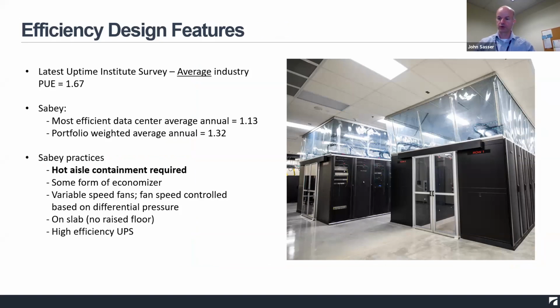So I've been with Sabey for 17 years, and we've been leasing data center space to customers for over 20 years. And efficiency has always been something that's very important to us. The latest Uptime Institute survey, and this is as of 2019, so it may be a little bit dated, but I don't think it's changed much, is that according to their survey, the average industry PUE was 1.67. At Sabey, our most efficient data center average annual PUE is 1.13, and our portfolio weighted average annual is 1.32. And people have talked about PUE, and I think a lot of people understand what it is, but for those who might not understand, it's essentially a measure of energy overhead. So a perfect PUE is 1. Anything above 1 indicates energy being used by something other than the IT equipment.